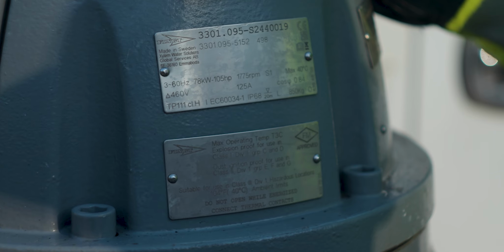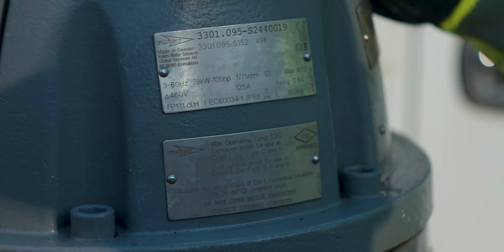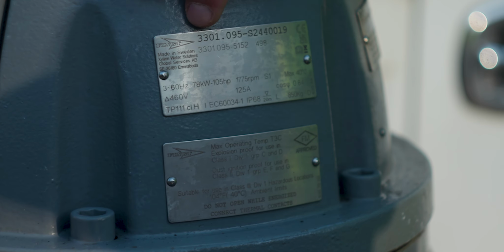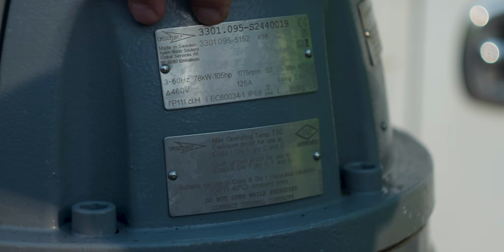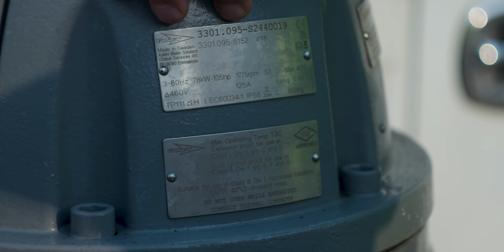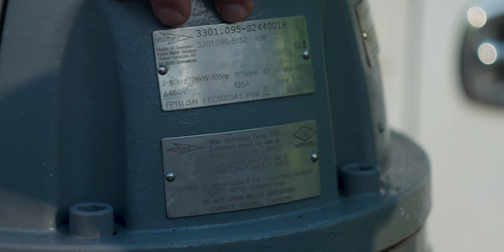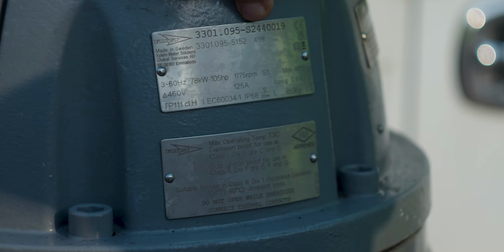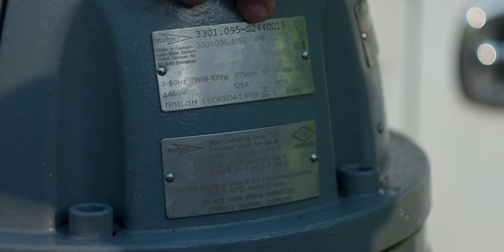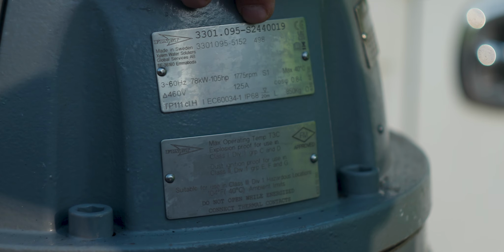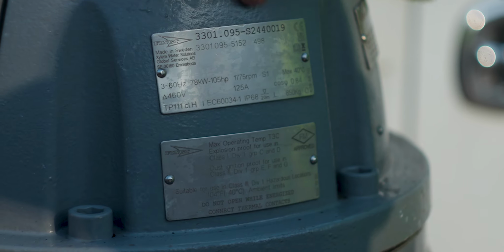This is the pump data plate. It has all the pump information on it, like we go over in the O&M manual. The first part is your pump model number, the motor version, which is 095, and then the serial number, which has an S designation in front of it. The S just means it has something special on it. On these pumps, the special item is the 498 millimeter special trim impeller.